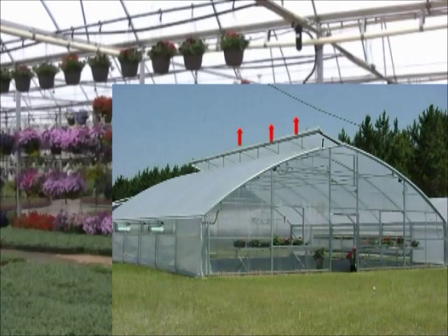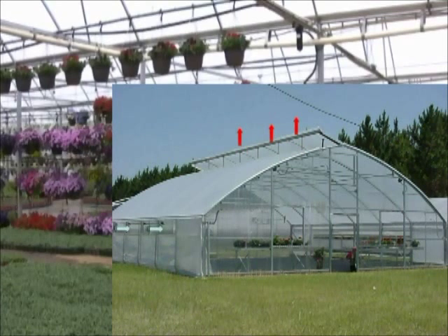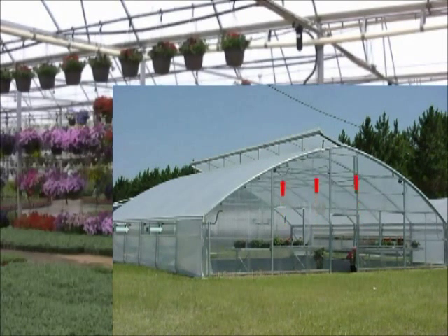As the cooler outside air comes into the greenhouse, it's being heated by solar radiation. As the air temperature rises, it pushes towards the top of the house and eventually exits the roof vents, creating a sort of chimney effect to the system. The movement of this hotter air out of the roof vent creates an additional vacuum, causing more outside air to enter through the wall vents.